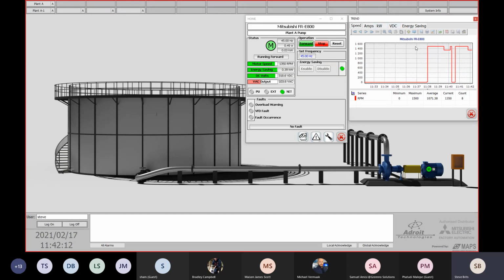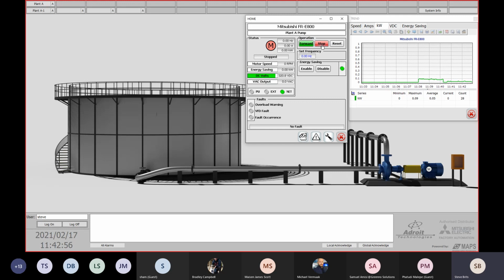And I can show you the speed. There we were on 50 Hertz, we went down to 45 Hertz. We enabled the energy saving back on 50 Hertz. I've gone down to 45 Hertz. But we can see quite a big difference on our amps being consumed and also our kilowatts being consumed. And that's running the same motor, just enabling one setting on the VFD. And that basically covers the energy saving with the Mitsubishi VFDs.